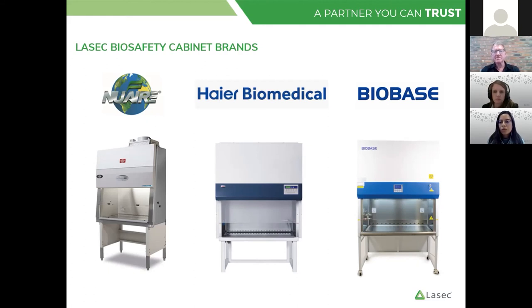Some customers purchase the smoke tubes just to do an in-house verification that the airflow is more or less okay — it's a lot better than a piece of tissue paper on the sash. It at least shows that you've got inflow and downflow. Whether or not you're measuring velocities, on a well-maintained cabinet these things don't normally go out of calibration that quickly. A very important test for a B2 cabinet would be the smoke test to make sure you're getting inflow and that the exhaust fan is working. We recommend quite thoroughly to B2 operators that they have some way of checking inflow using smokesticks. There is a list for these tests and you need to do all of them — no half measures.